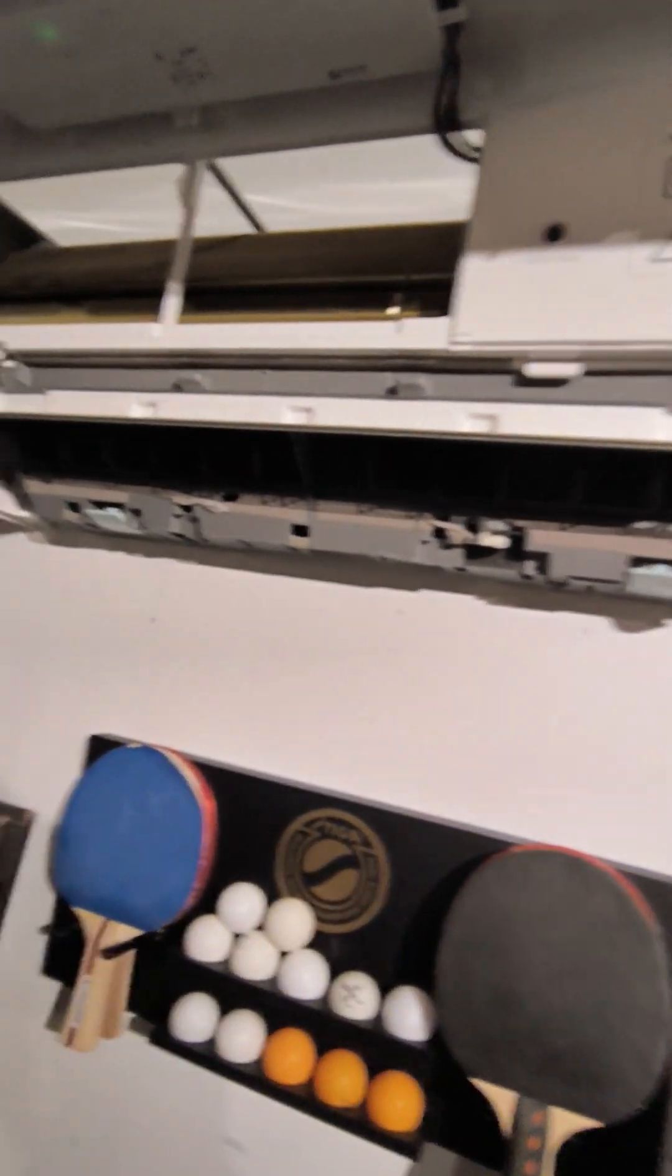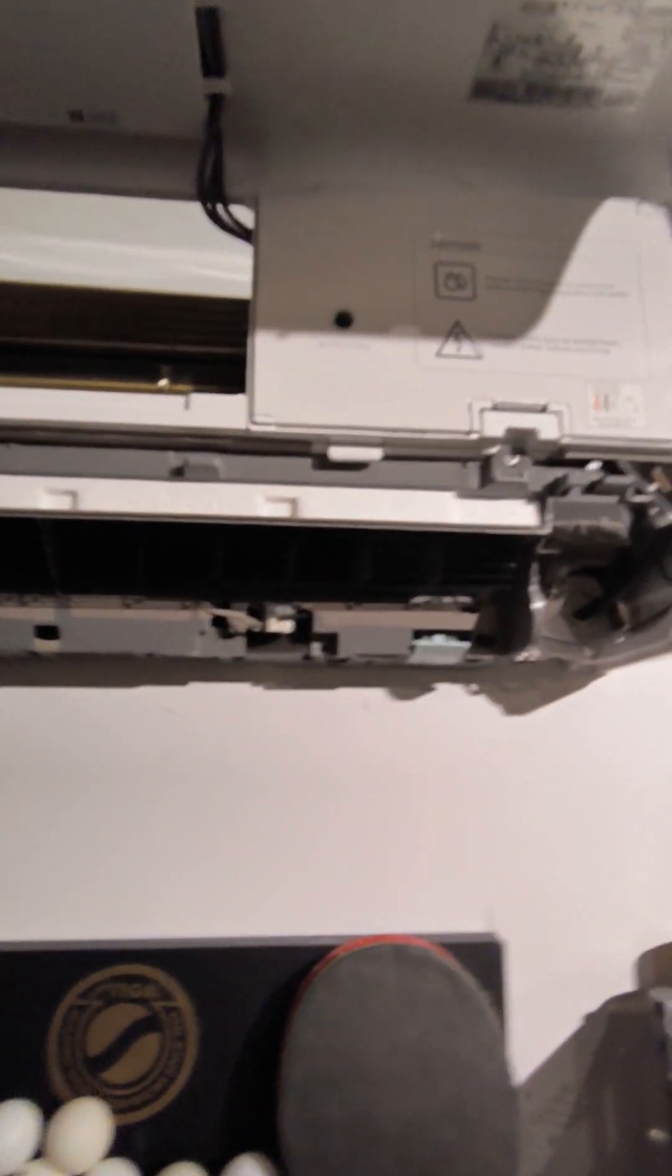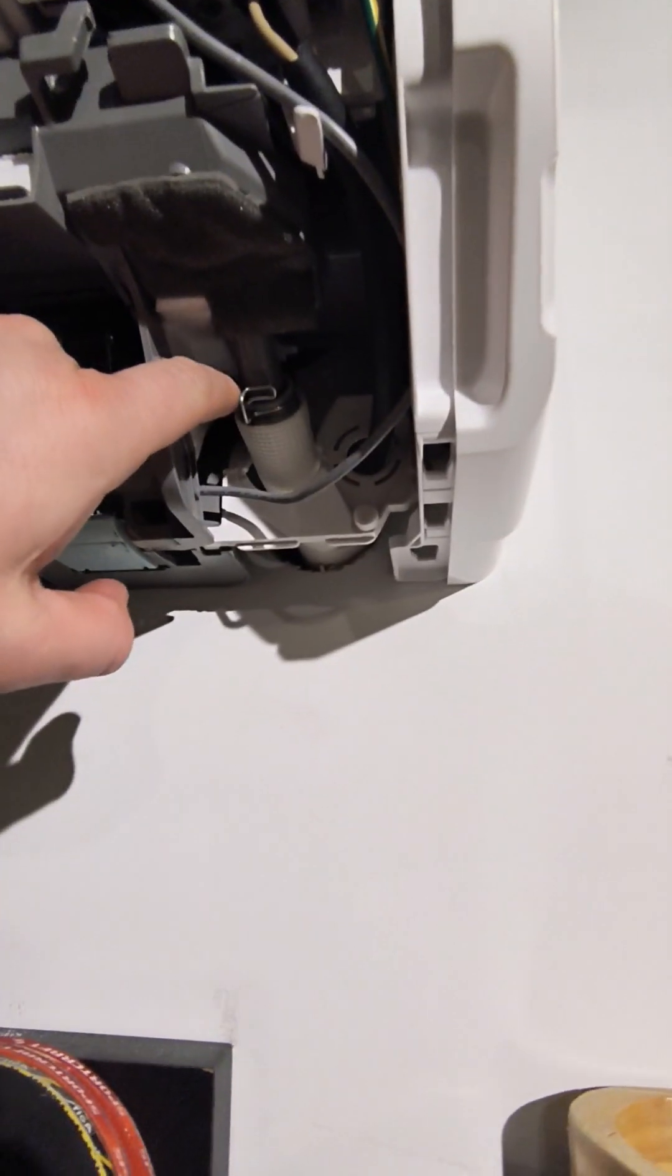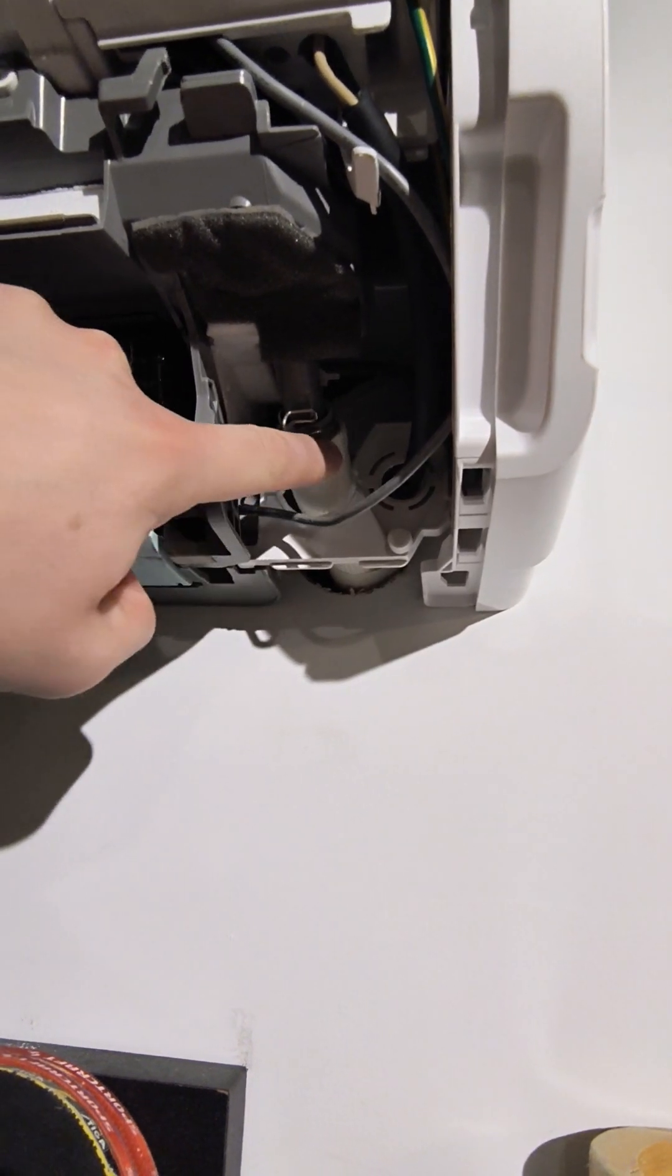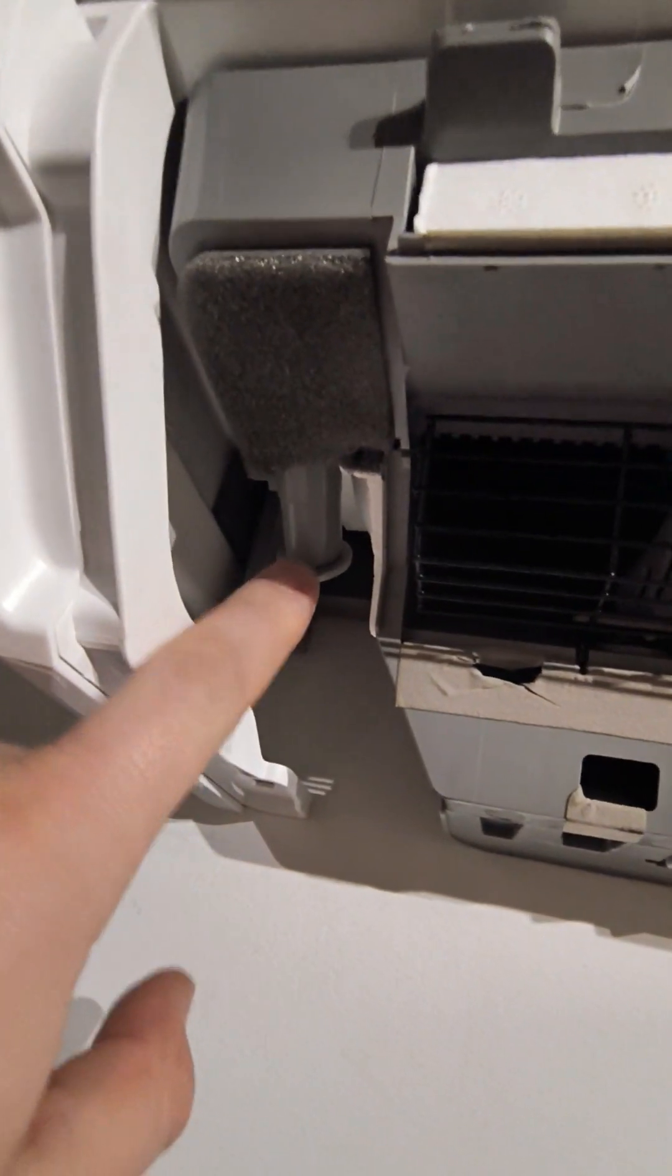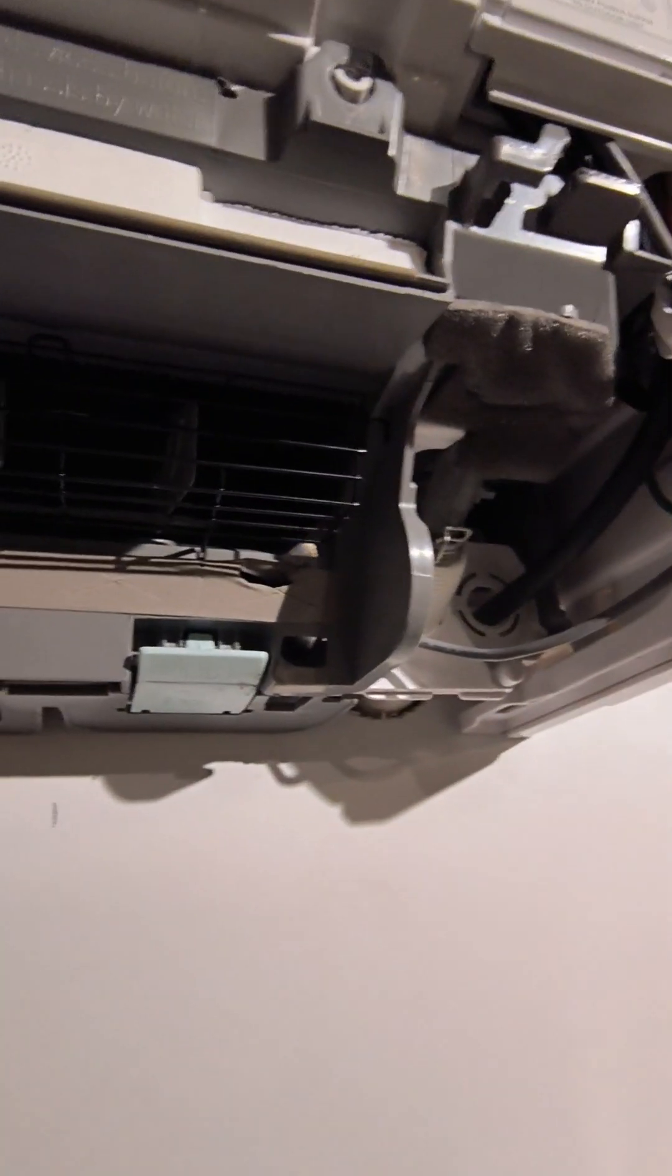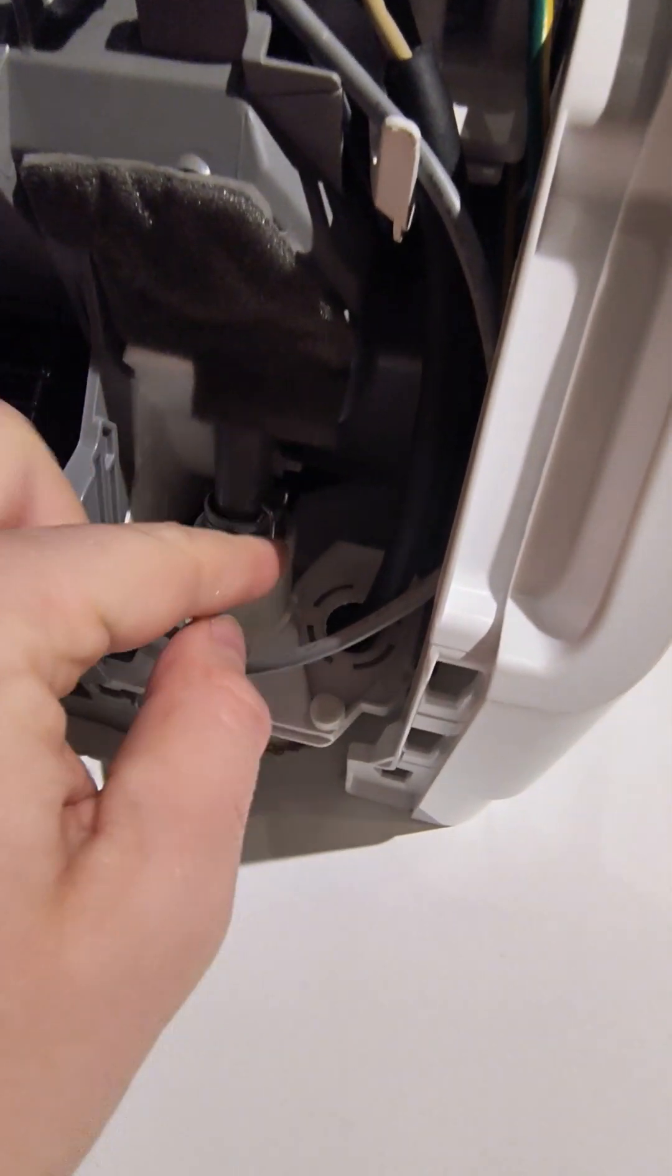So the clip piece, once those two screws are out, takes some finesse but it'll pop out of there. You'll see this is where the drain is typically connected to the condensate drain pipe. It sometimes might be on the other side depending on the install, but this one has a plug in it right now so it can drain from either side. The way we set this one up it went out the right side, so that's got the plug in it and this has the drain hose.